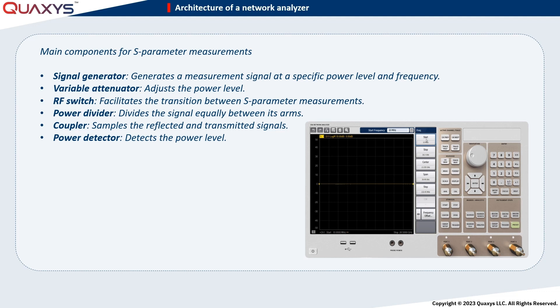Let's begin with signal generation. The signal generator serves to generate a measurement signal at a specific power level and frequency. This generator sweeps across the frequency range required for the measurement. Additionally, a variable attenuator is employed to adjust the power level.